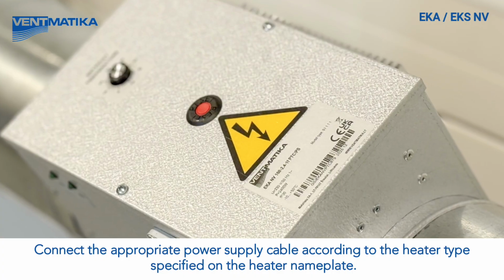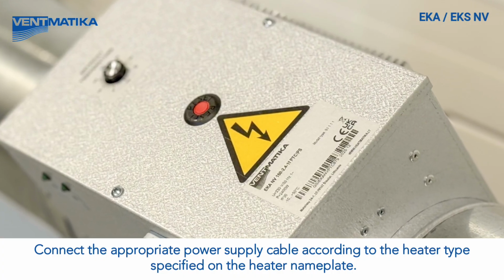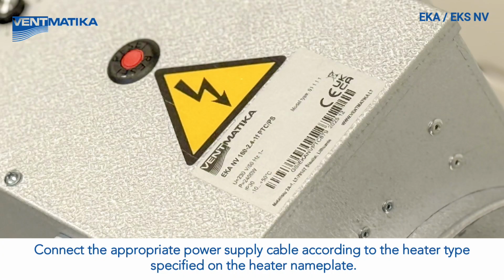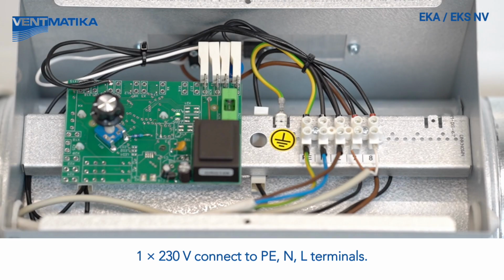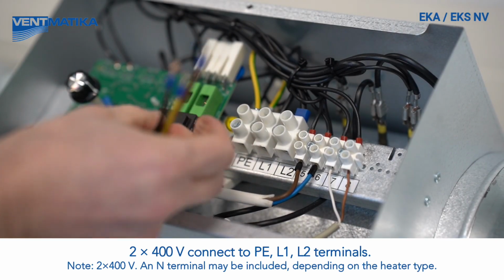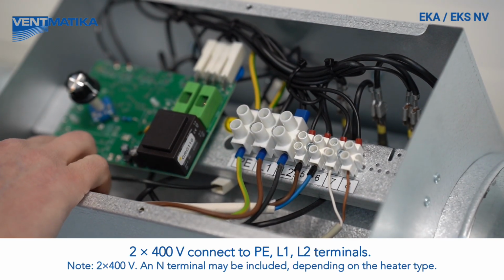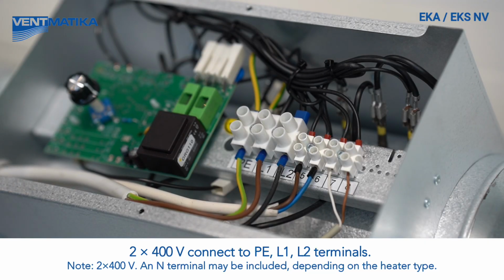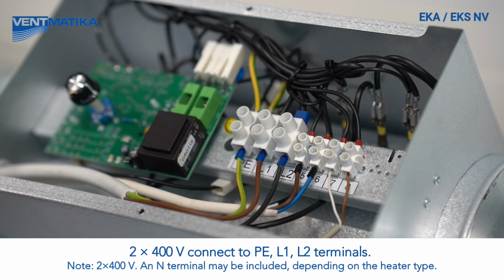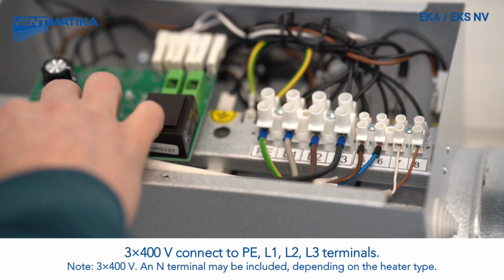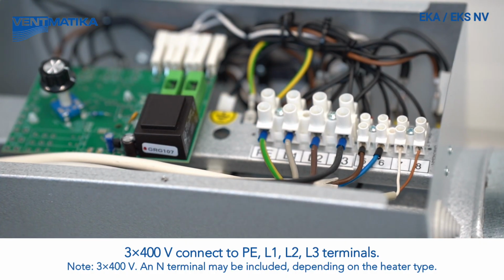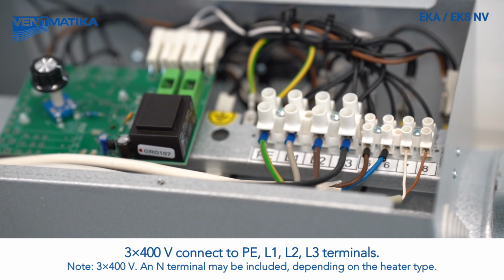Connect the appropriate power supply cable according to the heater type specified on the heater nameplate. 1 times 230 volts connect to PE, N, L terminals. 2 times 400 volts connect to PE, L1, L2 terminals. 3 times 400 volts connect to PE, L1, L2, L3 terminals.